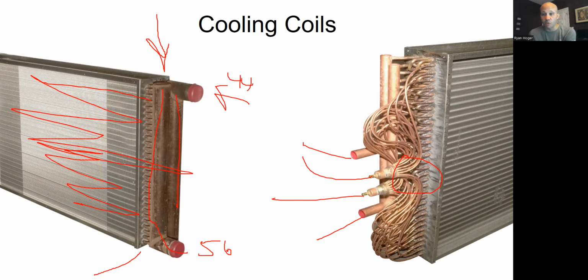Two, the piping system hopefully is insulated and hopefully has labeling that says chilled water or CW or something like that. And then three, you could feel the pipe. Just be gentle when you do that, because if it's 180-degree hot water, it could be really hot, obviously. So those are ways to figure out if it's hot water or chilled water. There's probably two of these coils in there, one for hot water and one for chilled water.